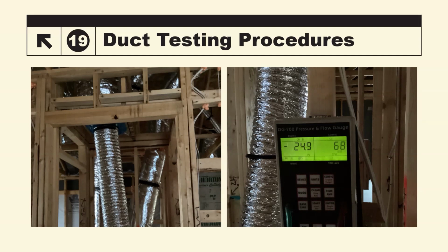These things have internal calculations, so even though you're at 18 pascals, it's giving you a number on the right-hand side that they're estimating. Well, if it was at 25, this is what I estimate it would be. That's still an allowable testing.